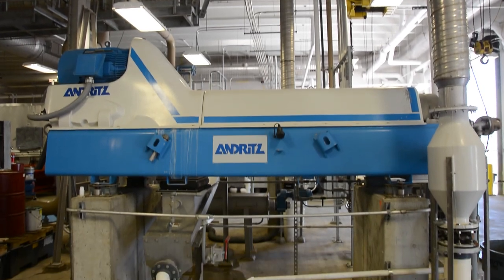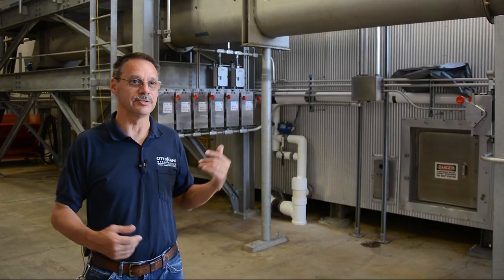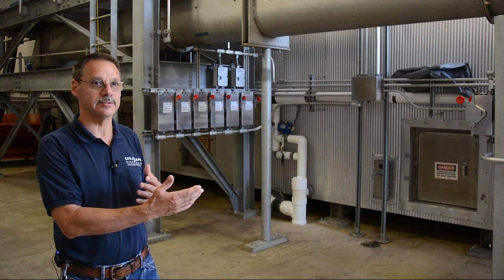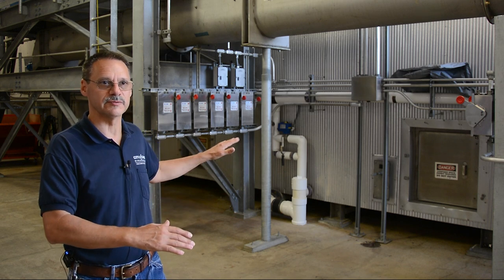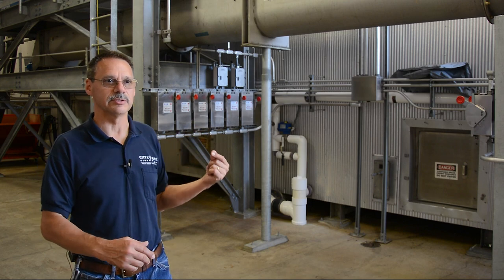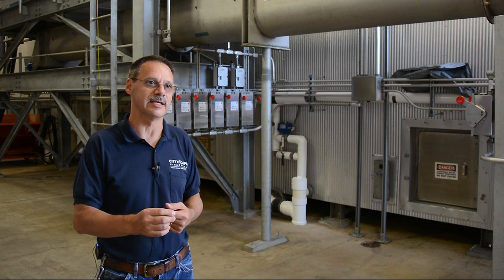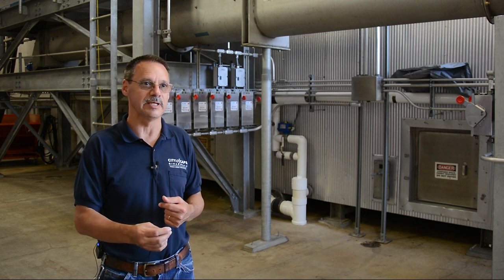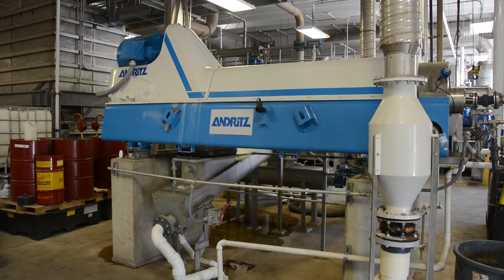The material is caked up in the centrifuge and from there we pump it into the biosolids dryer. The material is spread onto a belt inside the dryer about three inches thick and slowly moves from one end to the other. The temperature is taken at the end of the dryer and the percent solids are tested — the solids reach 92% solids to meet Class A exceptional quality material as defined by EPA, which is then licensed as a registered fertilizer in the state of Missouri.